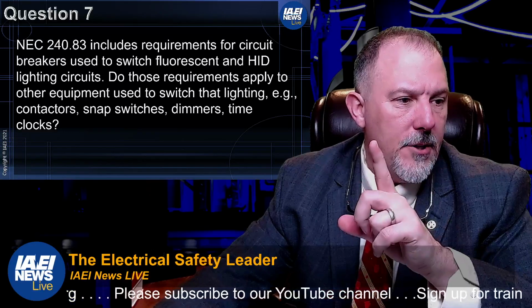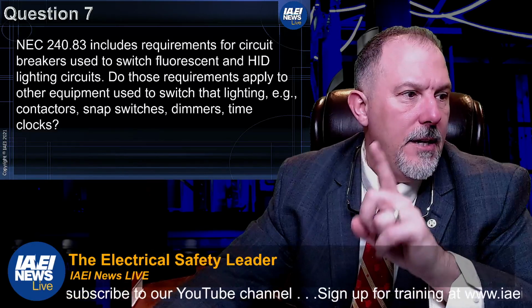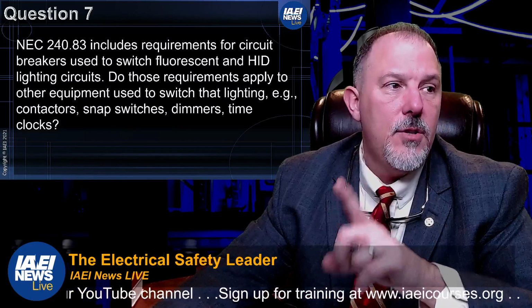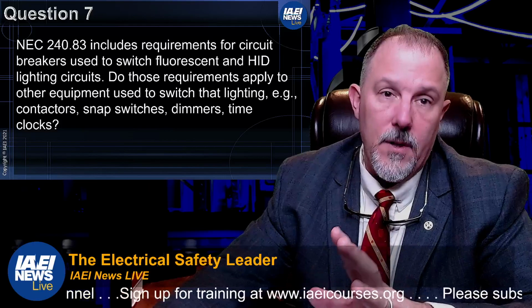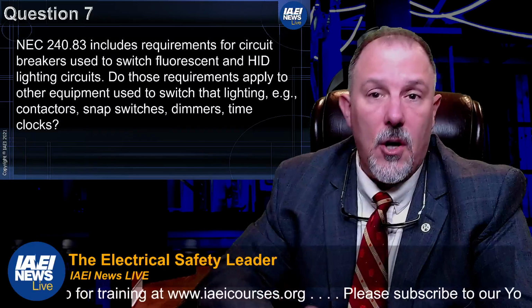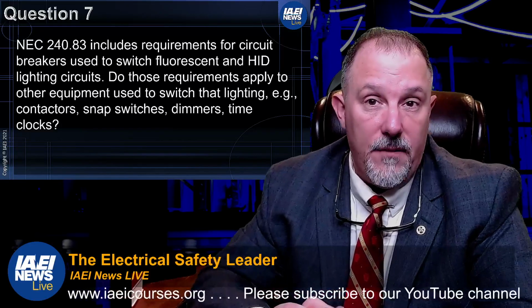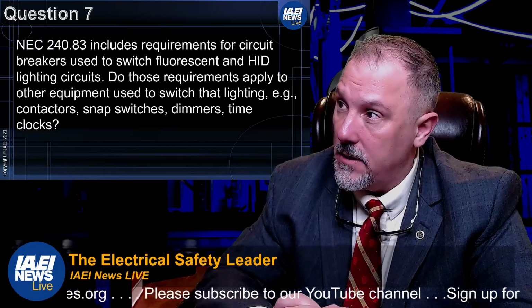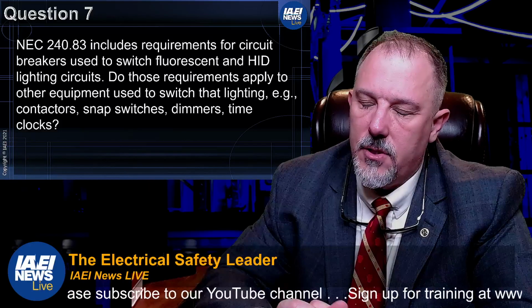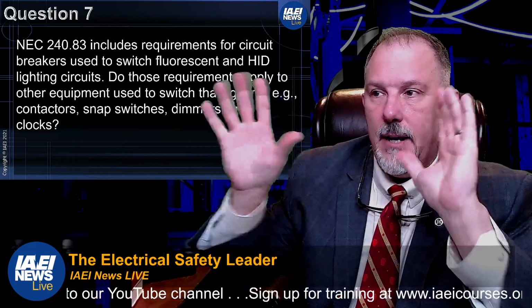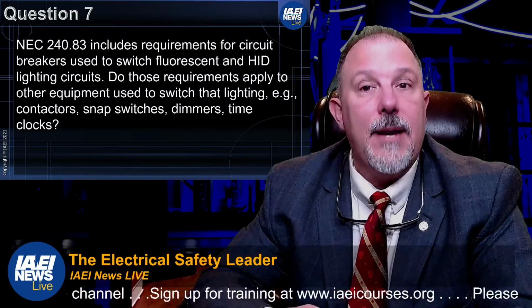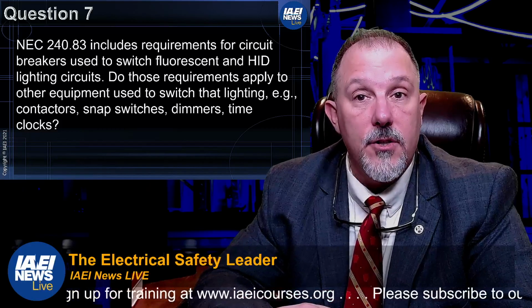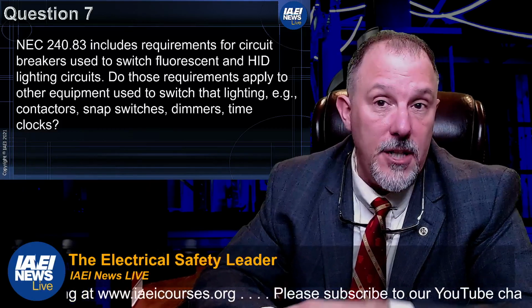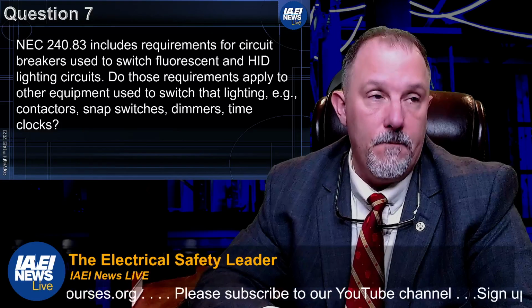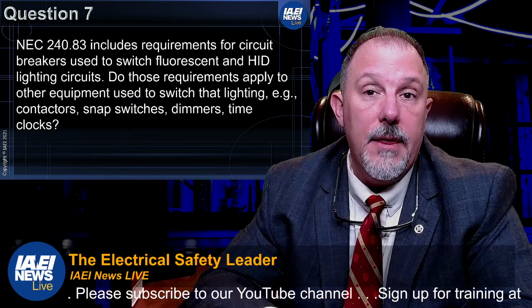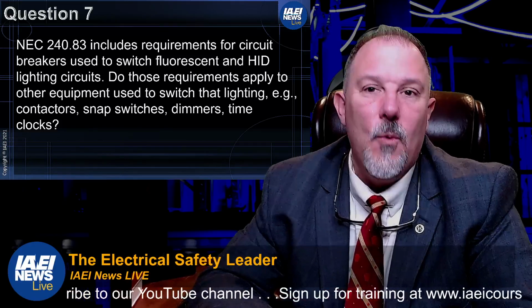So on the circuit breakers, there are definitely those requirements. Now, when it comes to other types of switches, you have to read the manufacturer's instructions on the switch. Those will tell you what they're rated for. In some cases, and I had fluorescents in my basement, and I put some of those occupancy sensors, and it caused a constant blinking. And I found that I was using the wrong switch for those lights. I actually changed out my fluorescents to a different technology, and the problem went away. But the switch itself, in the manufacturer's instructions, told me not to use them with that type of lamp.